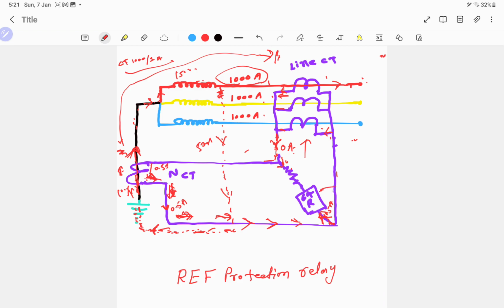And it will operate the REF relay, which will give a trip command to the circuit breaker, and it will open the circuit breaker, which could be at the primary side, at the secondary side, or at both sides. So we can protect the transformer by using the REF relay.